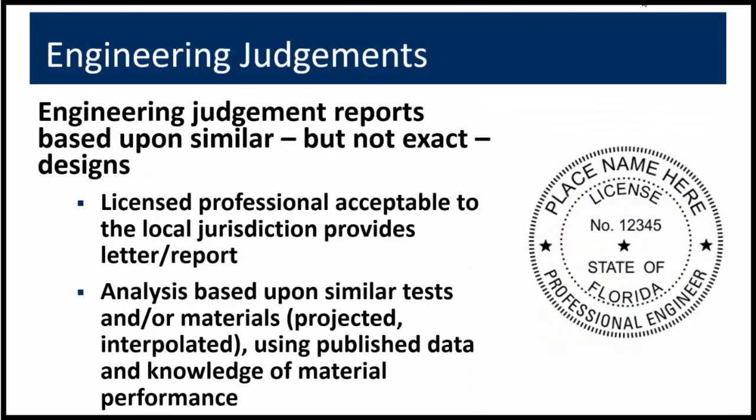If the field condition or design does not allow compliance with a tested or published design, the use of an engineering judgment is another avenue. This requires the analysis of the proposed materials and comparison of the proposed design to other similar designs which have been tested. This is applicable, for example, to the case where a specific brand of a material has been substituted with the product from another manufacturer, or changing the thickness of a material in a previously tested design. This approach requires knowledge of material behavior and fire test procedures. The local jurisdictions will likely require the licensed professional to stamp the submittal, but there's no assurance that the proposal will be approved by the local jurisdiction.